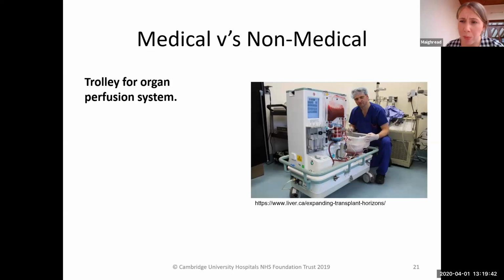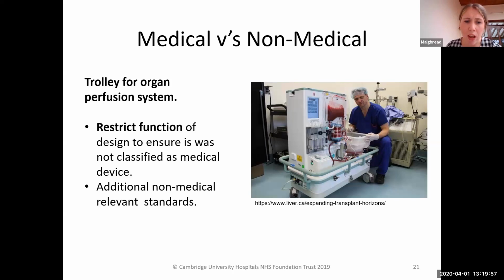So we were then approached to see if as a team we could design and manufacture a trolley for this system. And with this case, the question of whether it is a medical device or not came up. Looking through the regulations, we decided that if the functionality that the design provides can be restricted, then we can ensure that it's not a medical device.